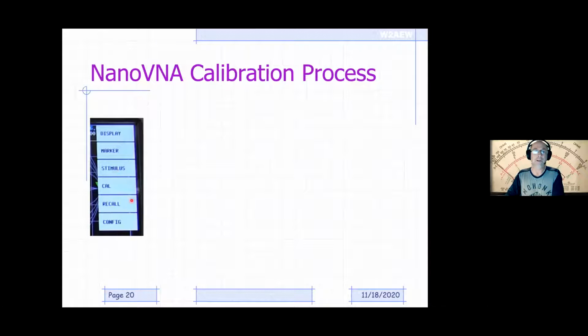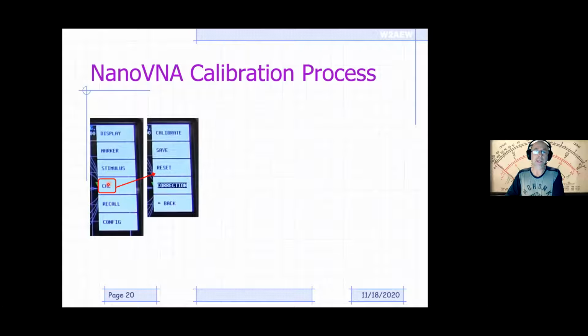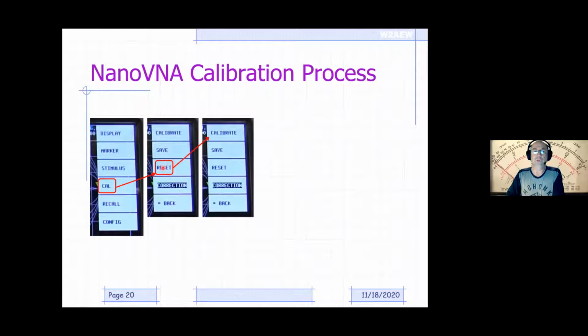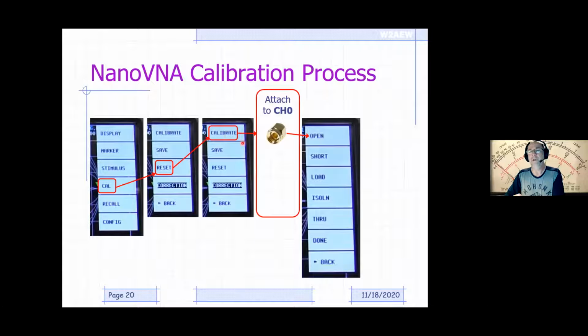So if you bring up the main menu on the instrument, it looks like this. And we start by hitting the cal button. That brings up the calibration menu. And you start by resetting to clear the current calibration. Once you do the reset, this menu will still stay here, and then you hit the calibrate button. Once you hit calibrate, it's going to prompt you to attach an open to channel 0. So there's a little open standard that comes with the instrument. You attach that, you hit open. Once you do that, you apply the short and hit short, and then apply a load and hit load. So these 3 cal standards, a 50 ohm load, a short, and an open, are all part of what comes with the NanoVNA as the calibration kit. And those are the ones that will do that first channel 0 calibration, again required for all measurements.